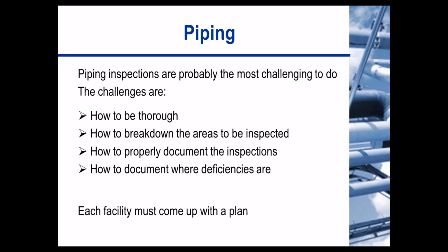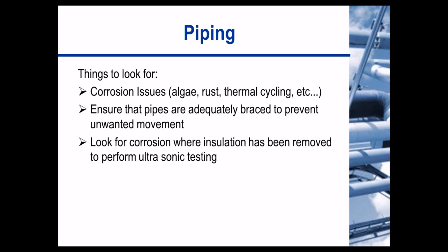Now, a little bit about piping. Piping inspections are probably one of the most challenging things for a facility to do. The challenges typically are how to be thorough, how to break down areas to be inspected, and how to properly document inspections and deficiencies. When dealing with these issues, the facility has to come up with a solid plan. Some things to look for are corrosion issues, and ensuring that pipes are adequately braced to prevent unwanted movement. Also, look for corrosion where insulation has been removed, sometimes even to perform ultrasonic testing.